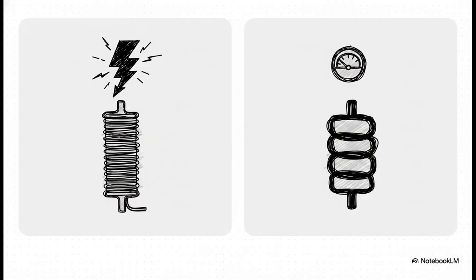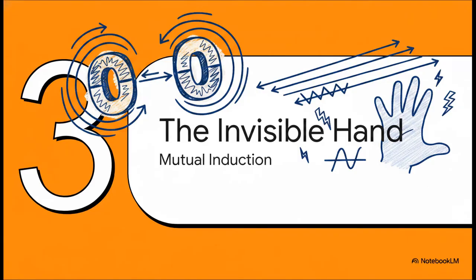Now, consider the stark physical contrast in the design of the windings themselves. It's not just about where they connect, it's about the wire. The primary winding, living out there on the dangerous high-voltage side, features a huge number of turns made of incredibly thin wire. On the exact opposite side of the spectrum, the low-voltage secondary winding uses a comparatively tiny number of turns. Keep this mental image of the mismatched coils in your head, because it is the absolute secret to how the whole operation works. Let's look at Section 3, the invisible hand.